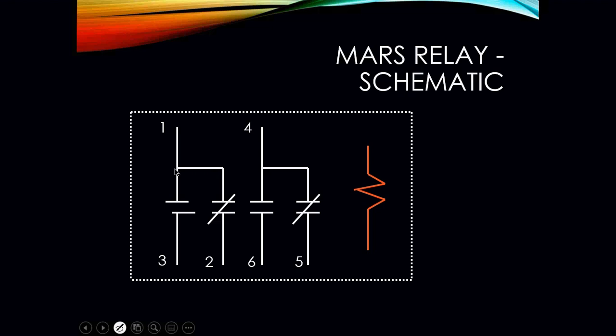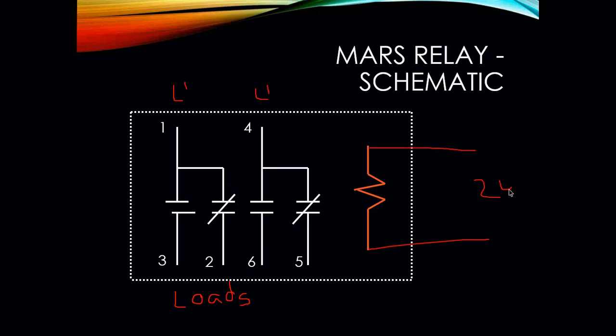It gives us our designations. Here is terminal 1 and terminal 3. It's normally open. Our terminal 1 and terminal 2 is normally closed. The same thing applies for 4 and 6 and 4 and 5. Terminals 1 and 4 are our L1s, our power coming in to our relay. Terminals 3, 2, 6, and 5 are all going out to our loads. Okay? And here is our coil, our power coming in. So I'm going to say here this is getting powered with 24 volts. Okay? So once I apply power to my coil of 24 volts, I am now energizing this coil, which is generating the magnetic field, which will make these contacts now switch position.